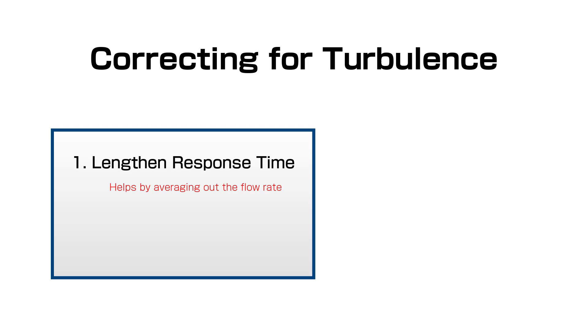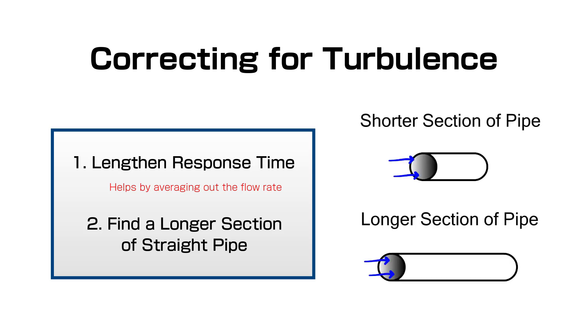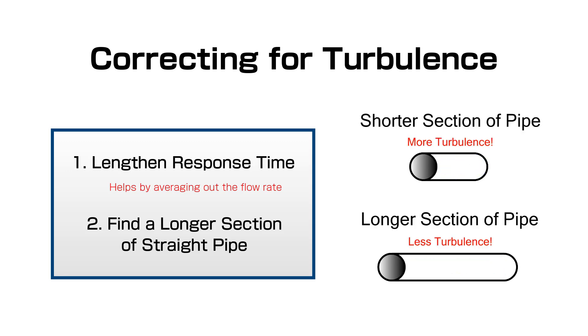The second thing to do is to maximize the amount of uninterrupted straight piping before and after the location where the flow meter is mounted. The more straight piping going into and out of the meter, the more laminar the flow will be, which is ideal for accuracy.